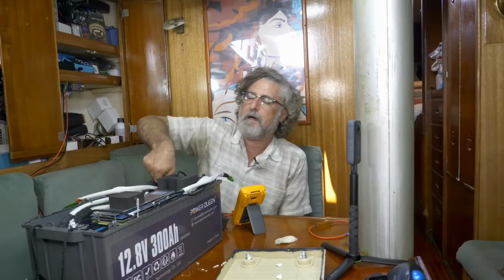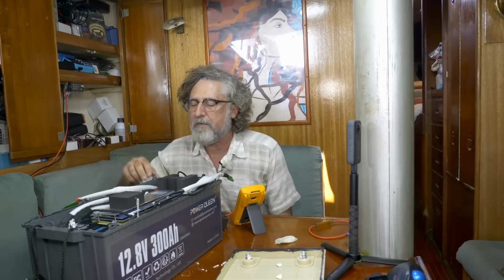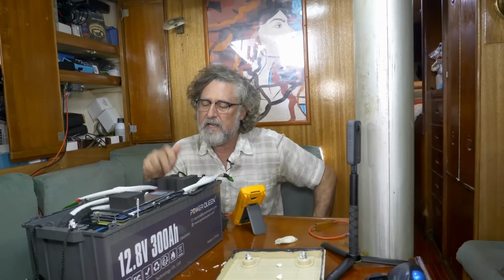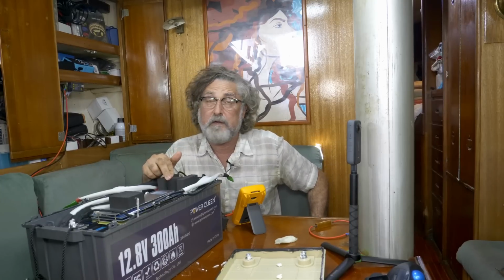Next step: well, this guy's still all charged up, I can see the whole top of it. I'm going to take this into the other room, we're going to hook it to my inverter. It's rated, even though it's a 300 amp hour battery, the BMS is only a 200 amp BMS, so we can't draw any more than that. We're going to draw 200 amps out of it and take pictures with the infrared camera.